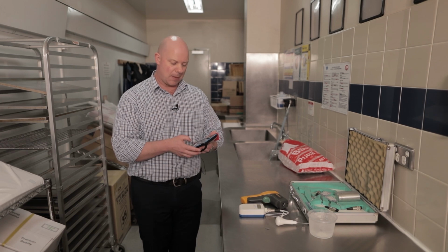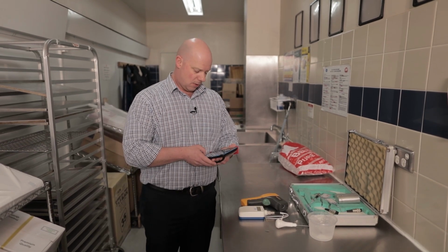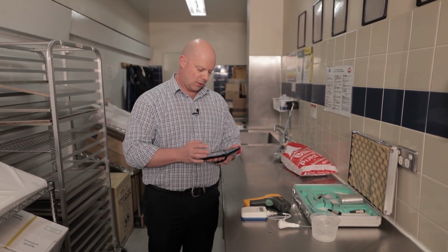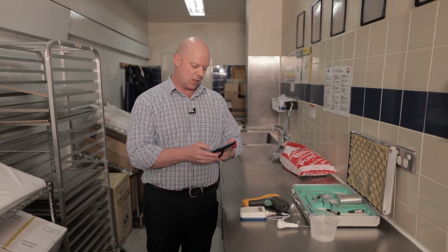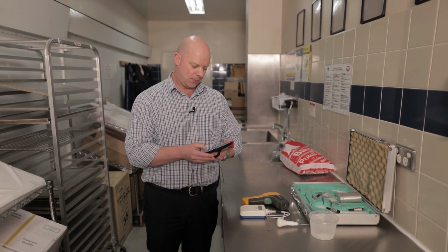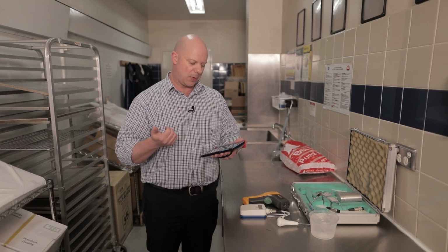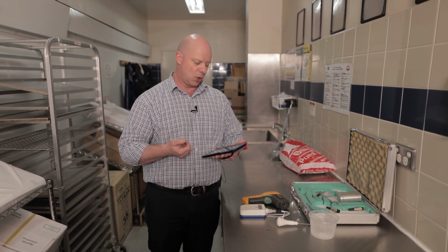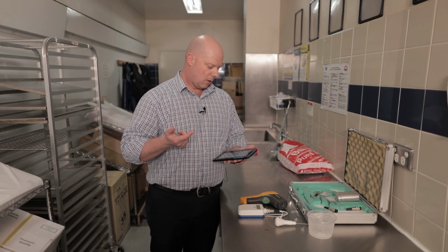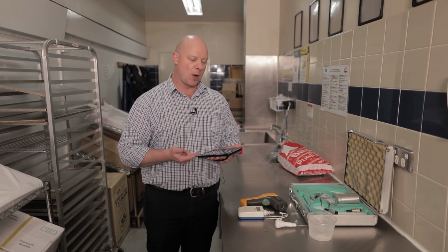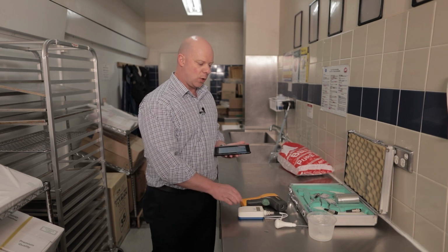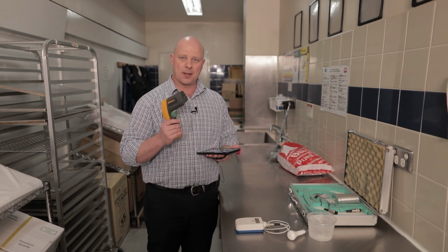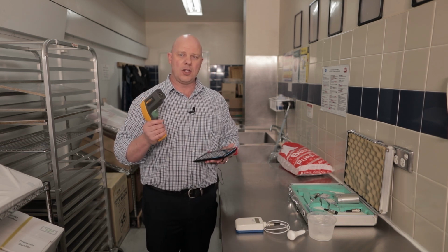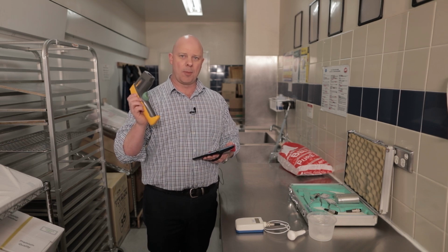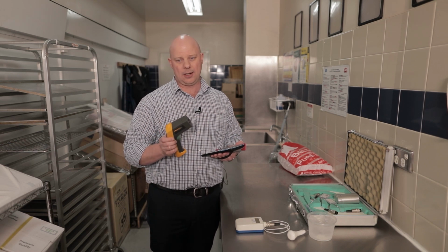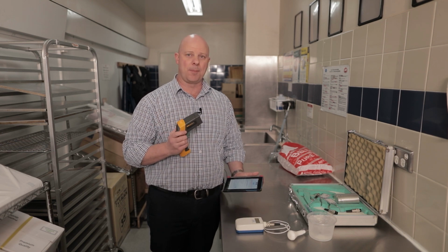So what if you do have some other equipment? Well, that's simple. What you want to do is when you go through the log sheet, there's 2 other checks that you can do. When it comes up with a test type, you can choose temperature probe, comparator and IR gun, or you can choose full temperature kit. With the first check that I showed you with the temperature probe only, there is no way with the equipment that you would have, which is only a probe and maybe an IR thermometer, there is no way that you can check the accuracy of your IR thermometer against your probe, because you can't do that when you don't have what's called a comparator pot.